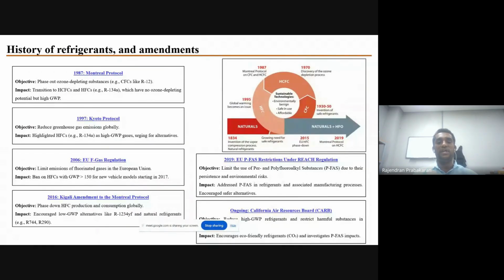So, history of refrigerants and amendments. Due to the environmental concern, in 1987, the Montreal Protocol initiated the phase out of ozone depleting refrigerants like CFC R12. At that time, the transition moved completely towards HCFCs and HFCs in commercial and automobile sectors. These refrigerants do not have ODP issues, but they have high GWP. Later, in 1997, the Kyoto Protocol was introduced because of the increasing global temperature. The major objective of that protocol is to reduce greenhouse gas emissions globally from refrigerants. In that case, they proposed to ban all the high GWP refrigerants in HVAC systems.